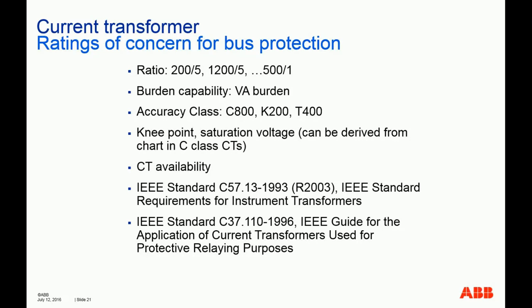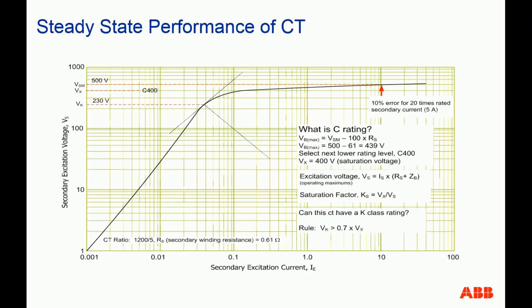Okay. And the last two points listed the relevant IEEE standard on CT, and most of you are probably very familiar already. So this is the CT performance curve that I talked about. Here is your knee point for this particular CT. It is the tangent at a 45 degree angle to the horizontal axis. So it's this point. And this 500 volt is your saturation voltage on the excitation curve, at 10% error, for 20 times rated current. And then this Vx, obviously for a C400 CT, is 400 volts. So it's here. This is just to show you the different numbers we constantly talk about for CT and how they are related to each other.